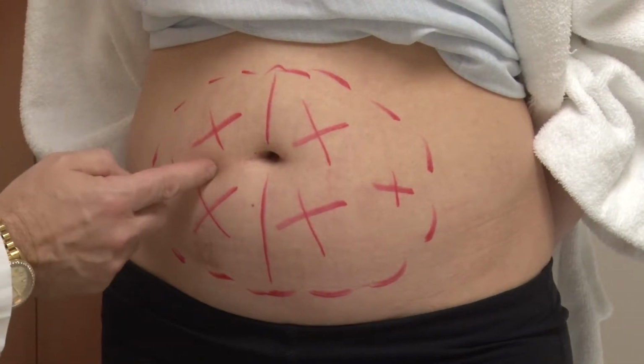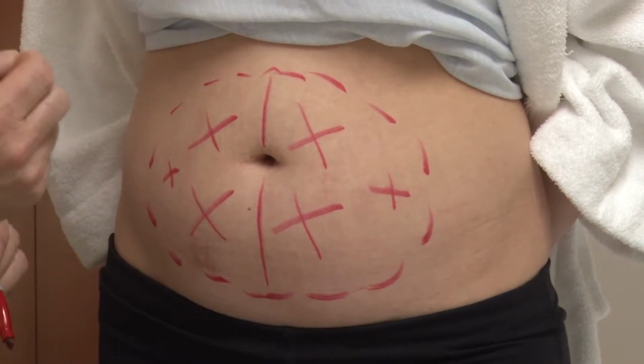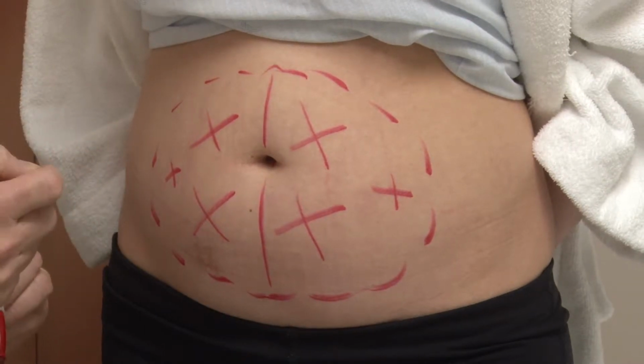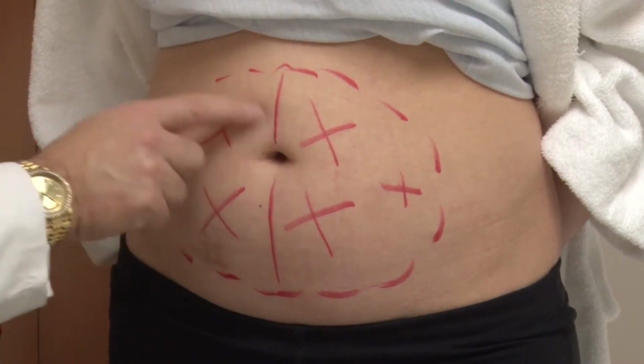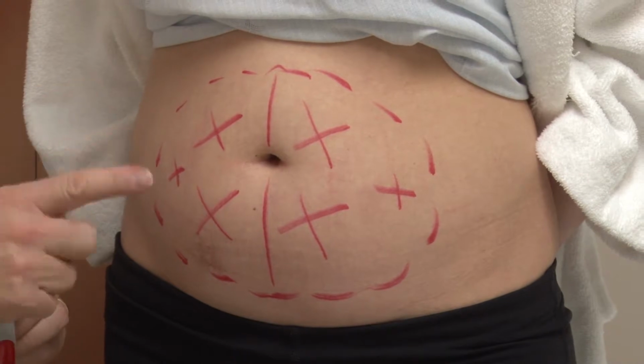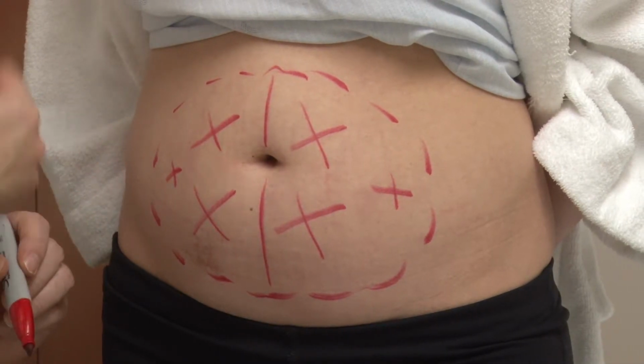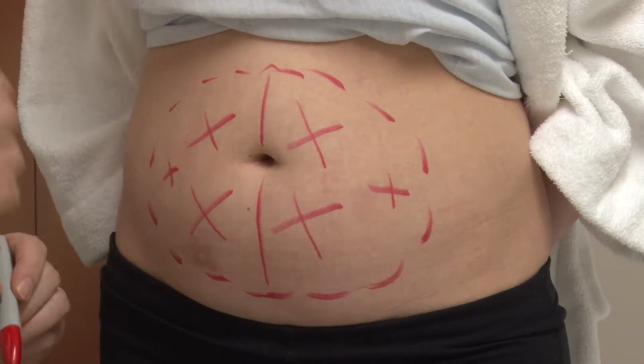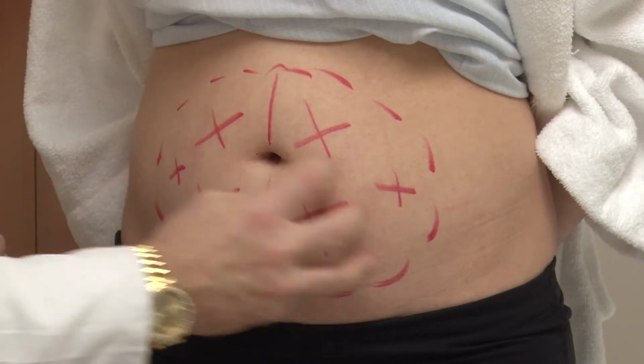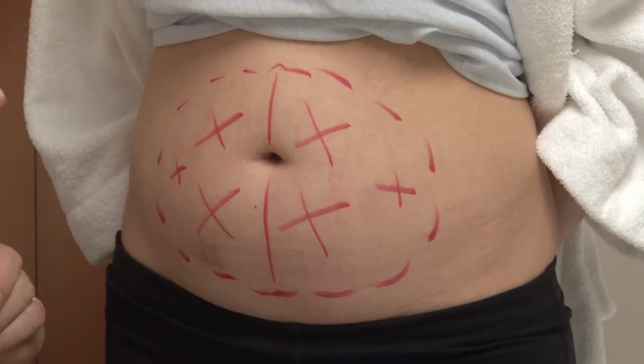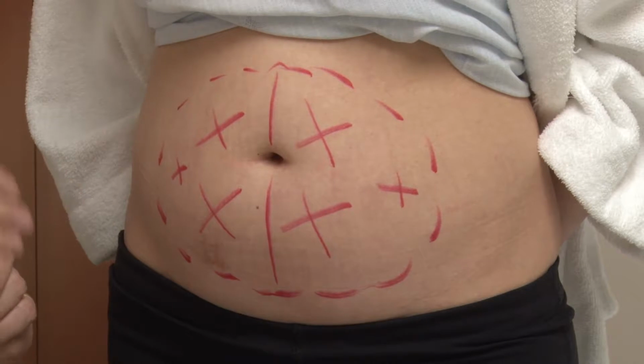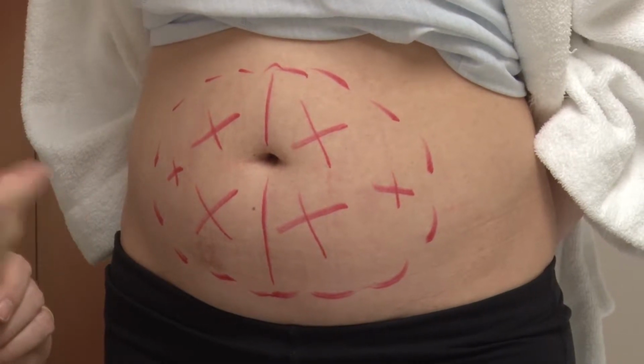We're going to spend 10 minutes on tissue with therapeutic high voltage pulsing. So you don't start the timer till you get to your end point, which is 42, 43, 44 degrees, and you're starting to discharge high voltage pulses. Then you start the timer. 10 minutes, 10 minutes. Each zone takes 20 minutes to treat, about once a week for 6 to 8 weeks, depending on your protocol.